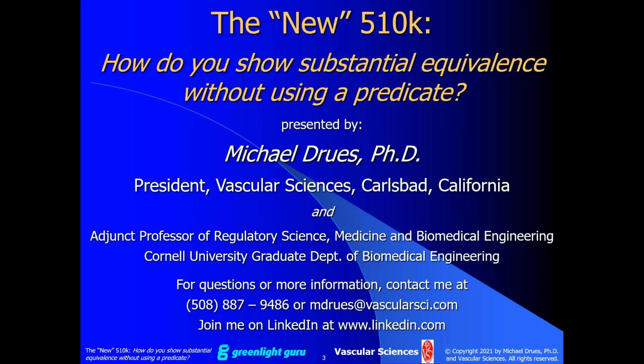So if your predicate device goes off the market, again, it's hard to respond unless we know why it's gone off the market. The regulation says that for us to make a predicate comparison, and it doesn't matter whether it's an SP 510K or any other kind of 510K, there has to be an active 510K, and that's it. The predicate device does not necessarily still have to be on the market. In other words, if the manufacturer of the predicate device decided to remove that device from the market because they've got a new version and that older version is no longer being sold, that's fine. You can still make a predicate comparison to that other device as a predicate, even though it's not physically on the market.